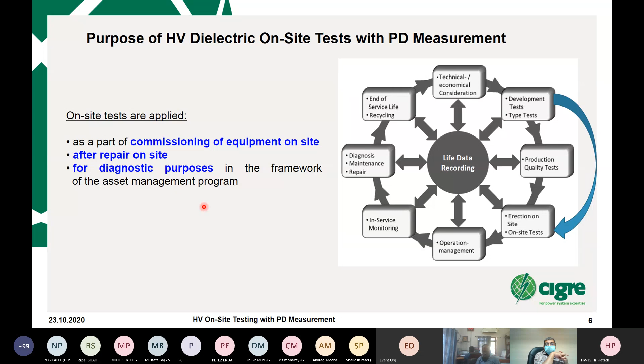This is not part of the technical brochure, but part of CIGRE is about partial discharges. And PD is a localized electrical discharge, and as I said, suitable for diagnostics. And as mentioned, there are different standards. In this case, the standard for the measurement of partial discharges and their so-called apparent charge is defined. The apparent charge is a charge which, if you inject it into the equipment, the PD measuring system can pick up as a current, and this current integrated is the so-called apparent charge. It is important to distinguish that this is not the real charge at the location of the PD. For example, if it's inside the transformer and you pick the signal at the bushing, there's a big difference between the two, and this has to be kept in mind.